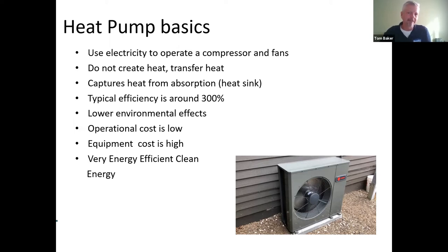It's actually stealing it, in a sense, from your backyard, and it's going to take it somewhere else. That's why it's called a heat pump. It absorbs heat, and then it pumps it to a different location. Now, just for clarification, you can get a heat pump that gets heat from the air. Some heat pumps, the geothermal, get it from the ground, where the coil lines, refrigerant lines, are buried in the ground. And in some cases, they will put it in water, in a body of water, to absorb the heat. There's enough heat in any of those three places to effectively heat your home.